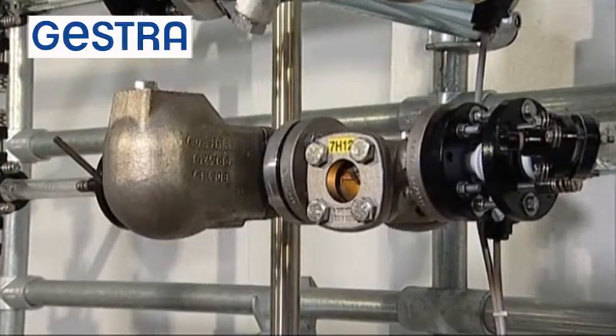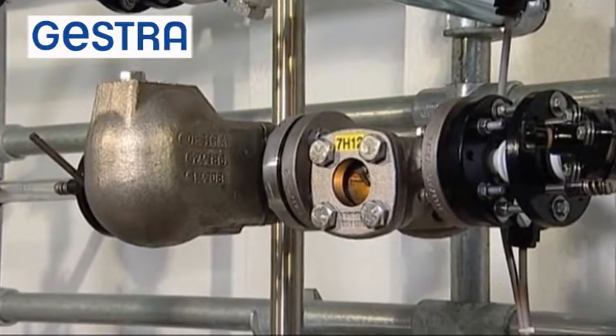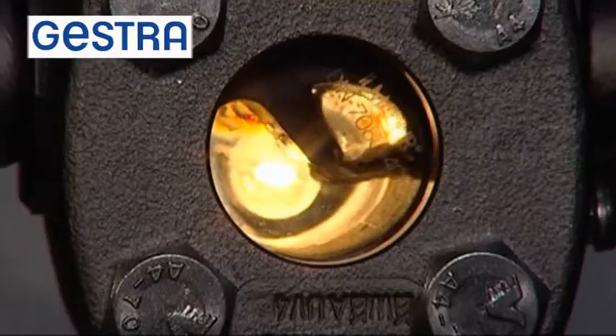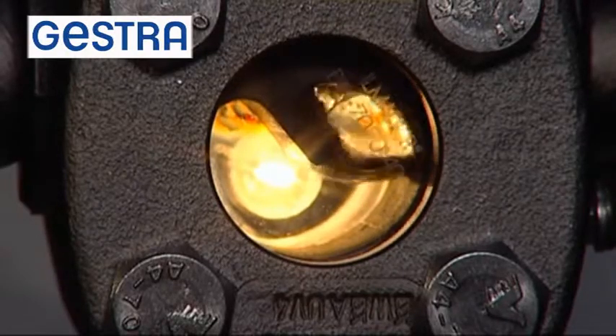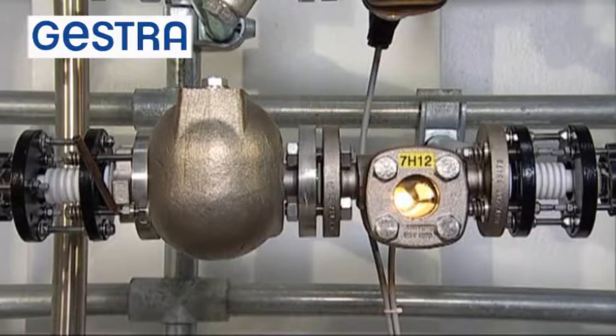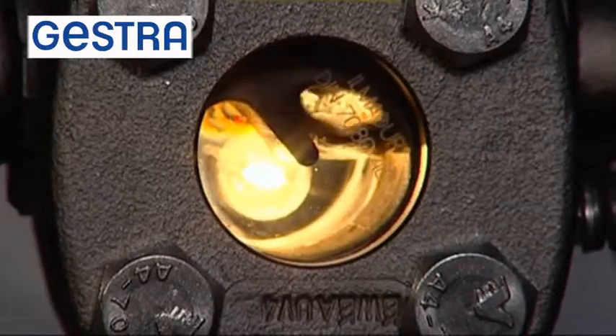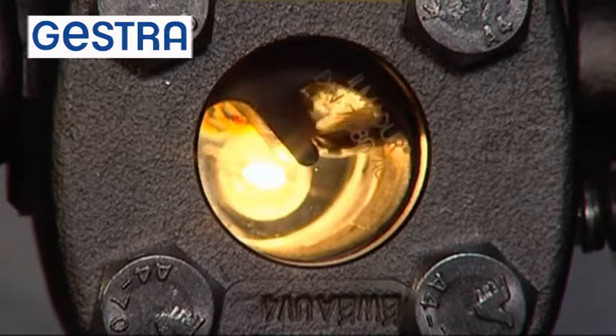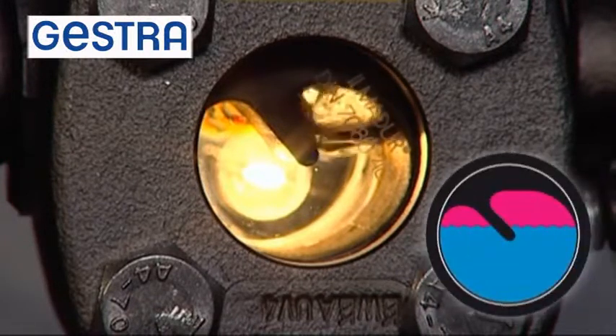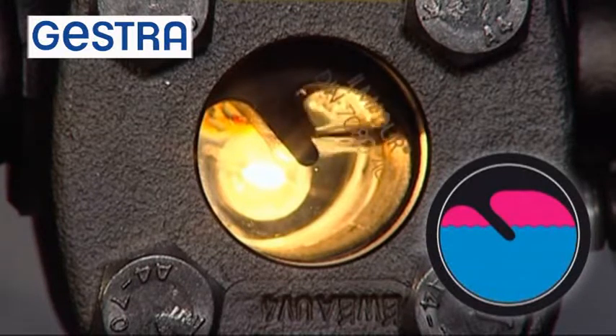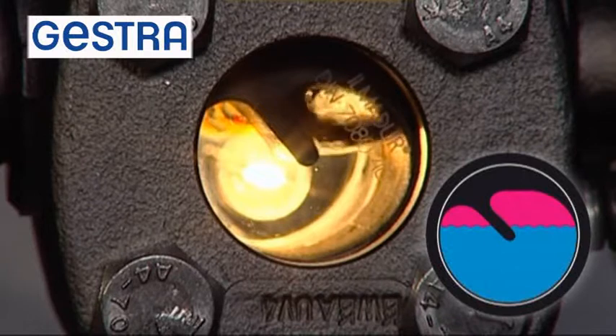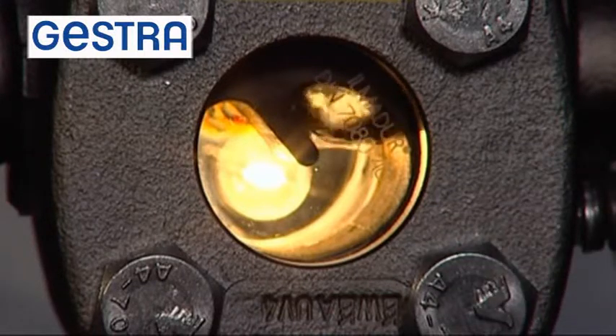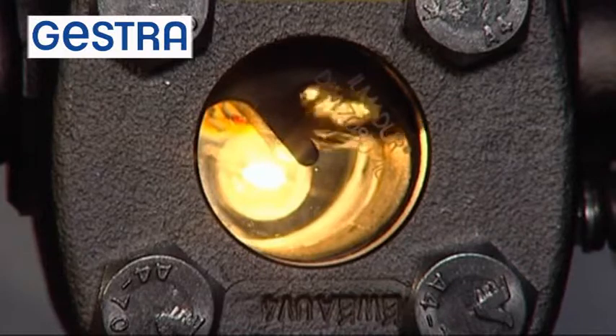This video presents the ball float trap, type UNA16. The float trap is preceded by a special sight glass, the Vaporscope VK16. This is used for monitoring the steam traps and making the flow processes visible. A deflector inside the Vaporscope sight glass forces the condensate to flow through a small siphon. A small steam space is formed in front of the deflector, and the deflector is slightly immersed in the condensate. The following steam trap is used for discharging only condensate. Steam does not pass below the deflector.